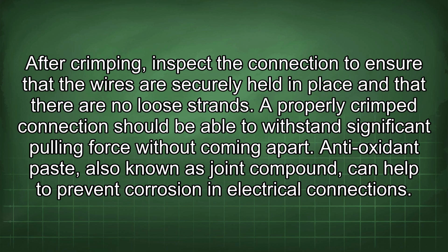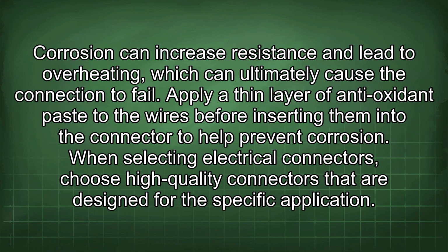Antioxidant paste, also known as joint compound, can help to prevent corrosion in electrical connections. Corrosion can increase resistance and lead to overheating, which can ultimately cause the connection to fail. Apply a thin layer of antioxidant paste to the wires before inserting them into the connector to help prevent corrosion.